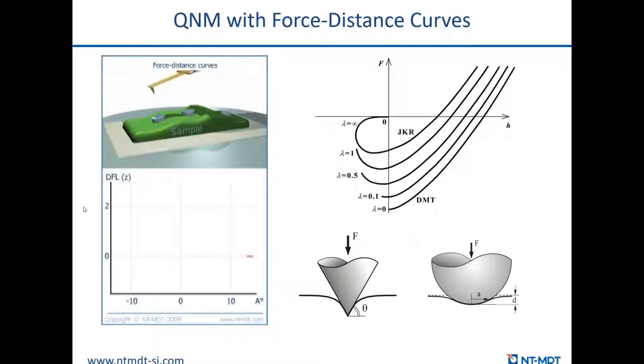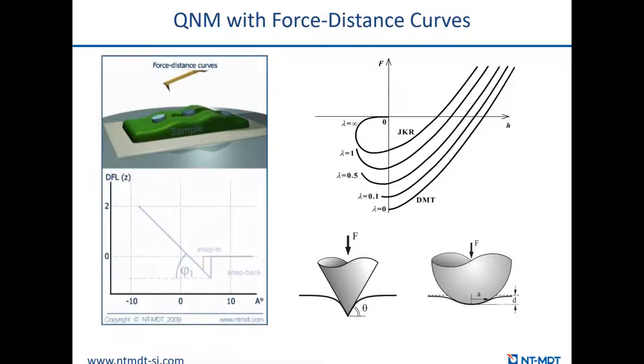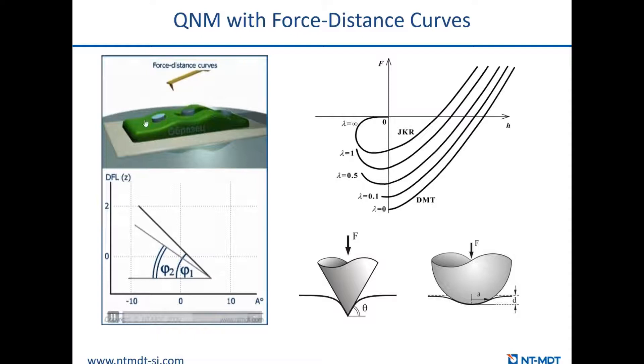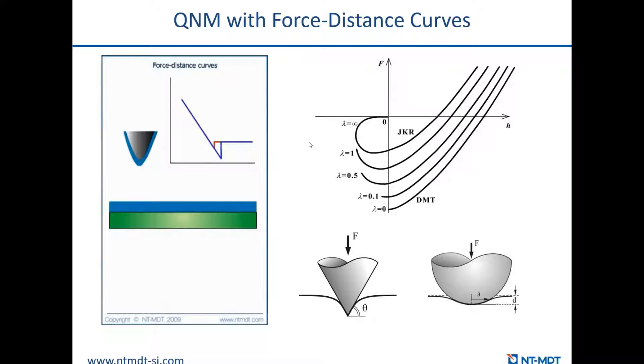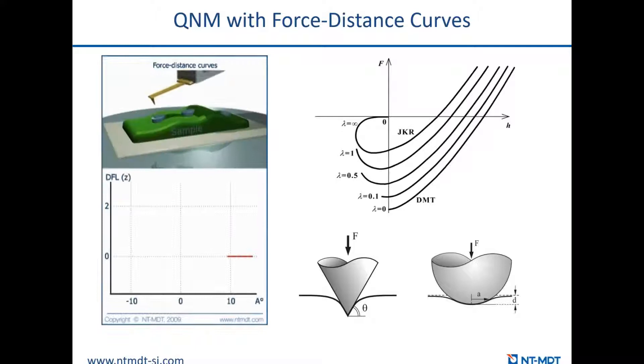Morphology and high resolution are useful, but we can also use the AFM tip not only to image the surface — if we vary the distance between tip and sample, we can probe the mechanical and adhesive properties. The tip moves up and down, and depending on whether the area is soft or hard, we get different kinds of force-distance curves. By applying one of the models of contact mechanics, we can evaluate quantitative numbers from these curves — this is called QNM, quantitative nanomechanics. These numbers include Young's modulus, force of adhesion, work of adhesion, etc.